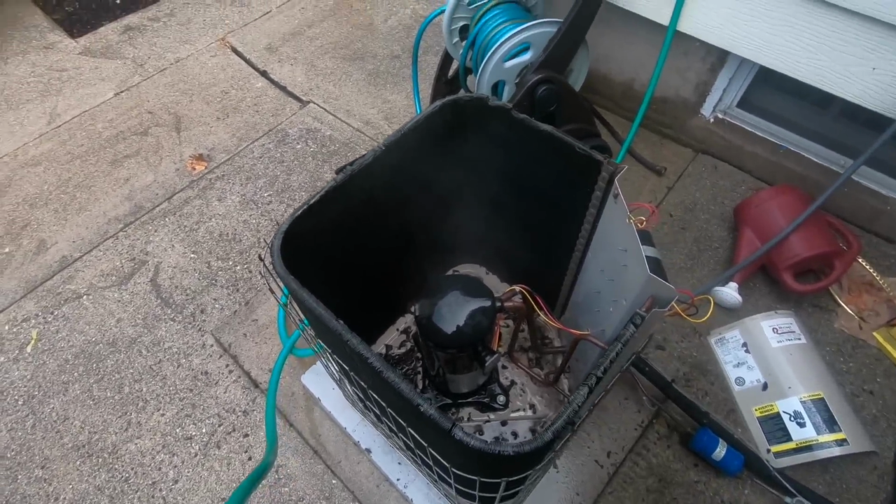So it's this door that goes down? Okay, so let me see what's on the left-hand side. The light is there. Okay. Get to the bottom. Okay. Turn the light to the right. I don't think I hear anything running. These lines don't feel like refrigerant's going through. Okay. Our ductwork's not cool. Yeah, we're still steaming, so.